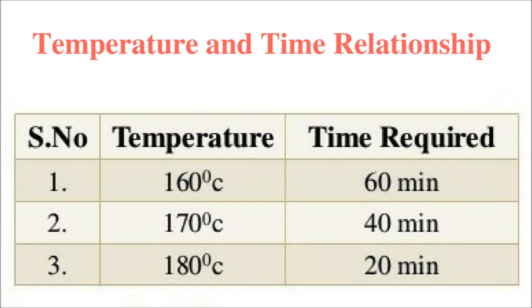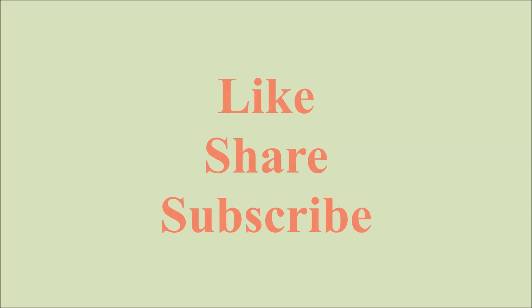This is the most important chart — you have to memorize it. If the temperature is 160 degrees centigrade, the time required for sterilization in the hot air oven will be 60 minutes. If the temperature is 170 degrees centigrade, it requires 40 minutes. At 180 degrees centigrade, it requires only 20 minutes for sterilization. The temperature and time relationship is very important — as we increase the temperature, the time required for sterilization decreases. As you can see: 160°C = 60 minutes, 180°C = 20 minutes.